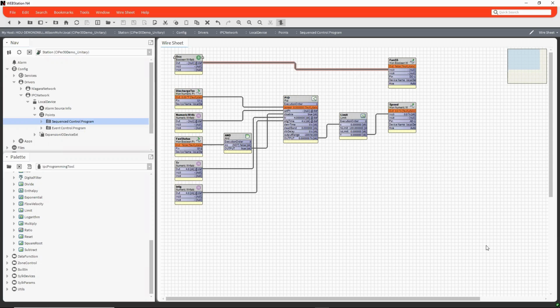So this is a typical fan start/stop that I set up. It's very basic unless there are other requirements in there, like freeze protection. If you have a fire alarm attached to it, typically I'll add those in there to disable the PIDs, to keep parts of the system from going into alarm.